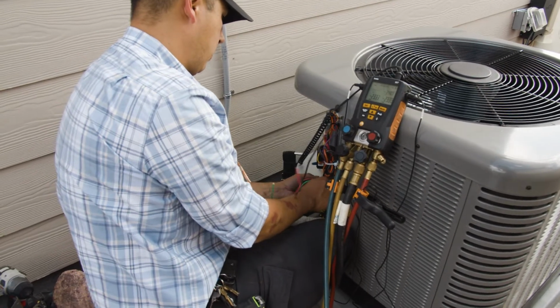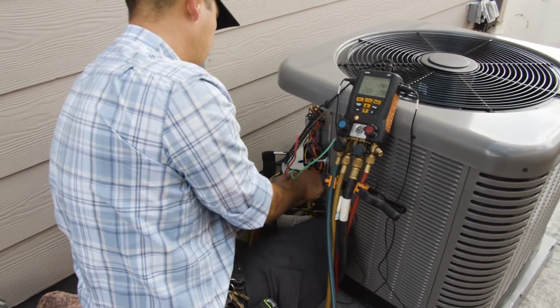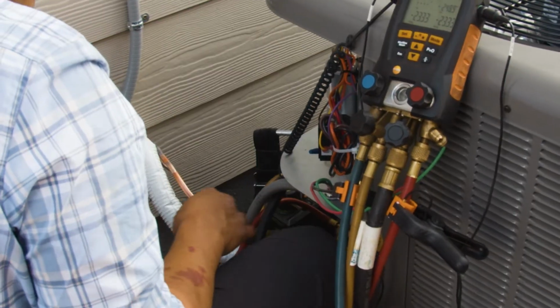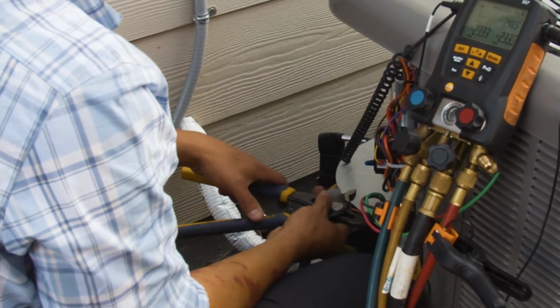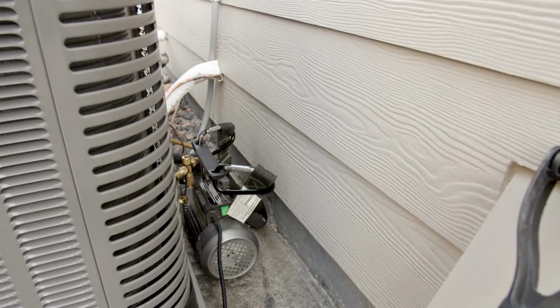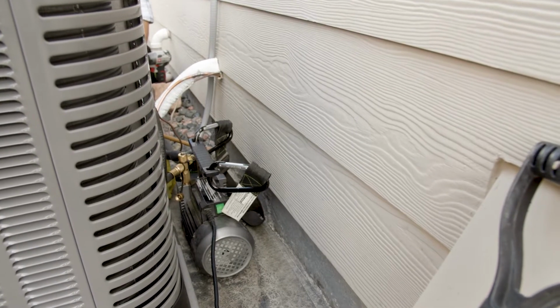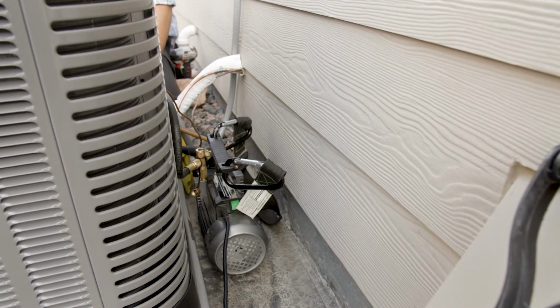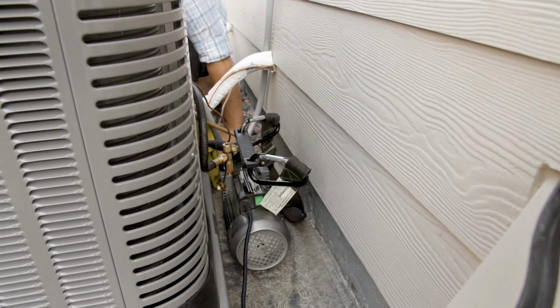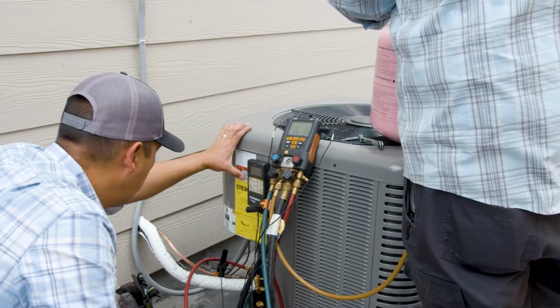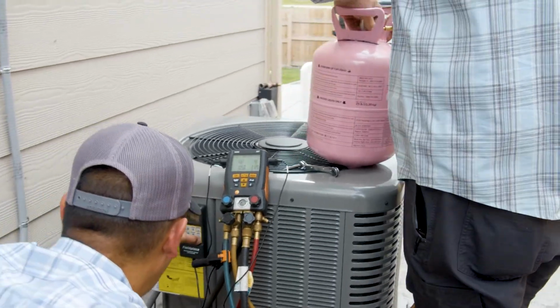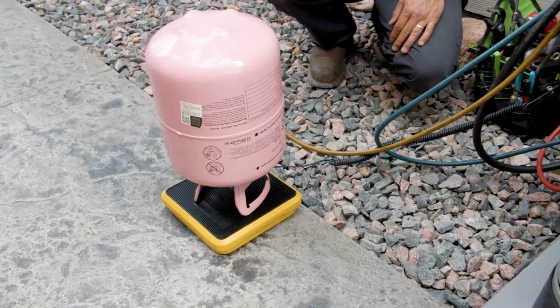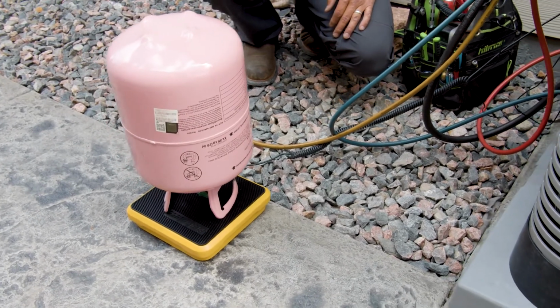Once we get everything connected, we have to do a pressure test on the system, make sure there's not any leaks, and then we do a nitrogen purge to make sure there's not any contaminants in there. Then we hook everything up and do a deep vacuum on the system just to ensure there's not any moisture or contaminants in the system. After that, we'll release the charge and add or remove refrigerant to get the charge exactly perfect so that the AC works properly.